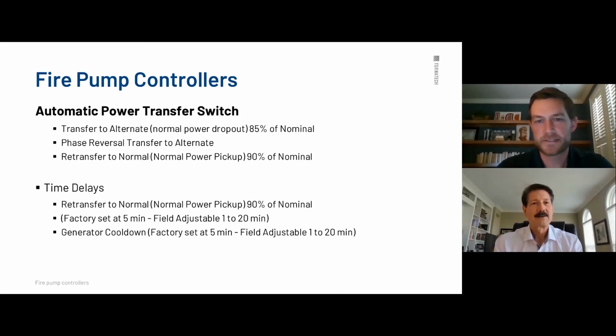I'd like to add one more thing, Cole, too. Sorry about that. On the automatic power transfer switch, when it gets down to 85% of nominal, that process initiates a potential startup on the genset itself. And there is a delay of 1 to 3 seconds that's field adjustable, because the one thing you don't want with a dip like that is to have nuisance starting all the time. So that's required by code, is to have a delay, but you can adjust it between 1 to 3 seconds.